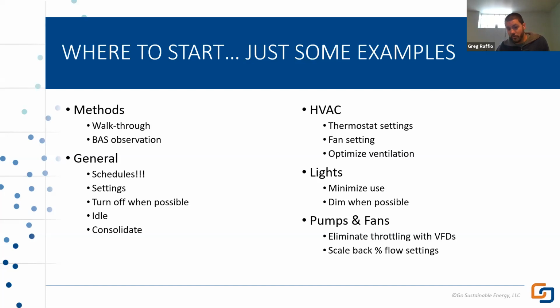So this is one of the greatest and easiest areas of impact we could be making right now: setting our buildings back. Common barriers are things like, 'we can't set this air handler back because of X, Y, or Z,' or 'Bill comes in at 5 a.m. and doesn't want to be hot or cold.' That usually puts a pin in the entire balloon.